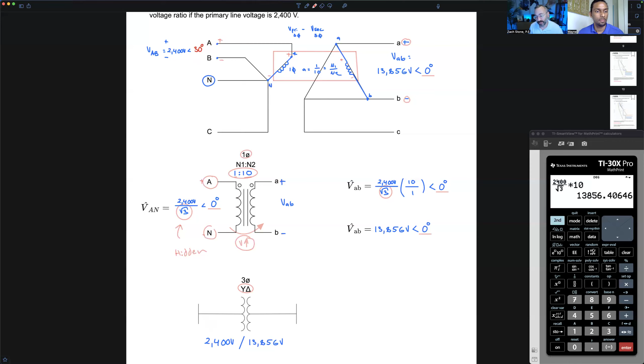This means the voltage applied across the primary winding on our Y side is not the line voltage, it's the line to neutral voltage. So we had to divide the line voltage by the square root of 3 to figure out what's the voltage actually applied on the primary of the transformer, the voltage that actually gets stepped up according to the single phase voltage ratio. Does that make sense? Yes, it does.